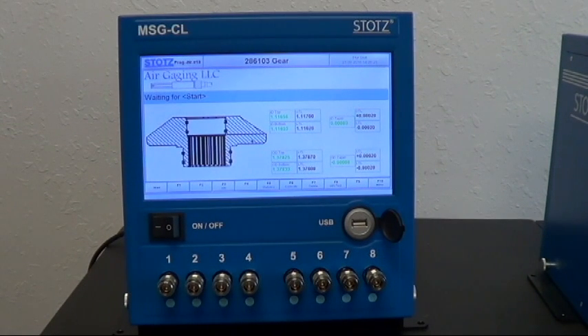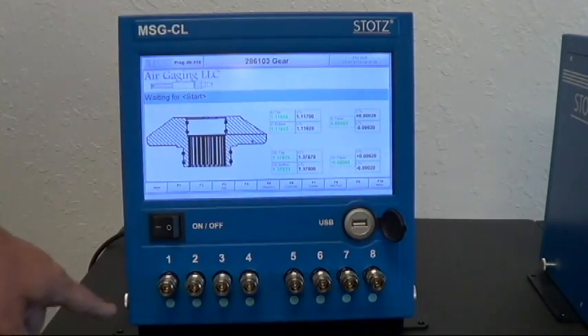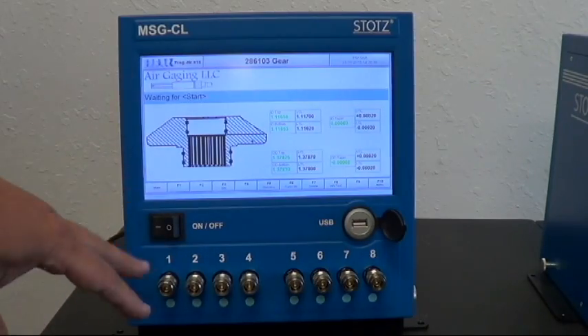Today I want to talk a little bit about the Stotz MSG-CL unit. This is a multifunctional pneumatic and electronic gauge. As you can see from the front here, we can have up to eight pneumatic channels. Those could also be switched to LVDTs or a mix-match of both.